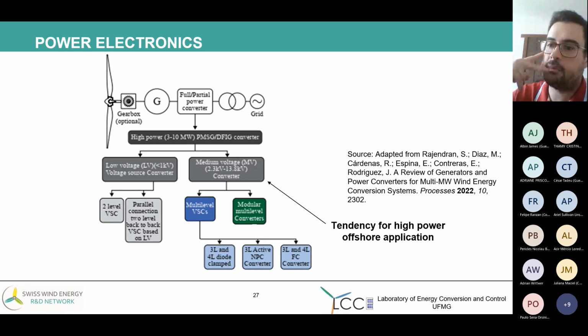The power converters can be divided in 2 groups: the low-level voltage source converters. What does low voltage mean? It's voltage below 1000 volts, 1 kilovolt. And the medium voltage converters between 2 and 13 kilovolts. These voltages are according to the grid and according to the generator.